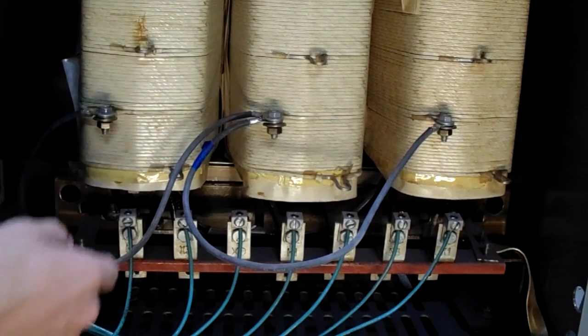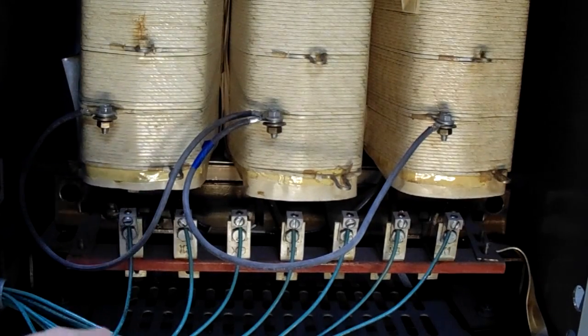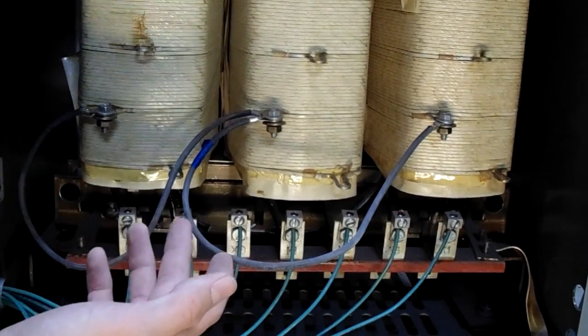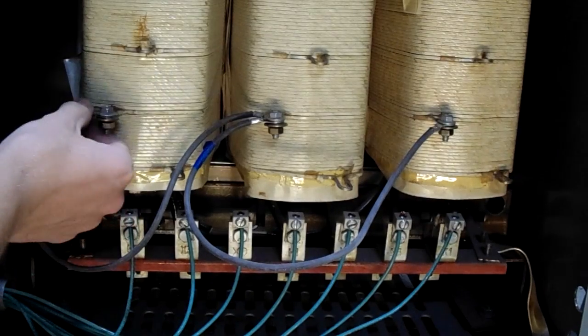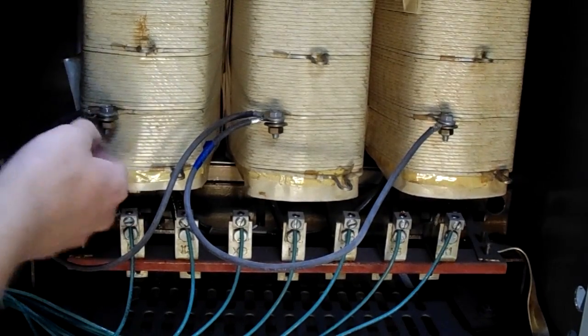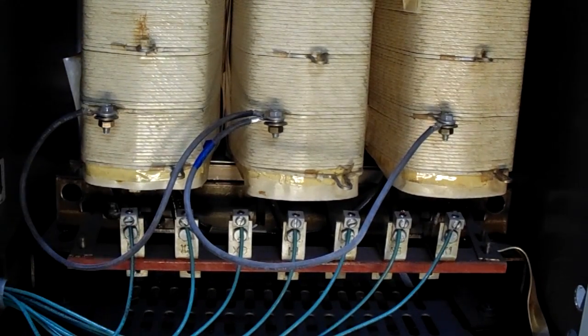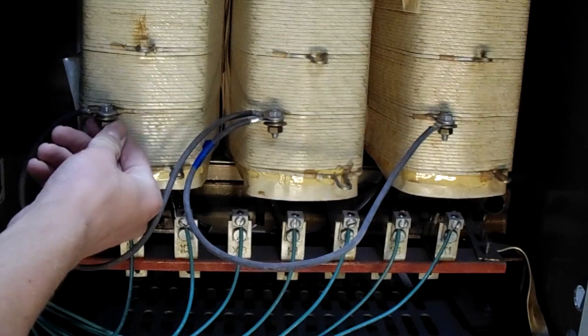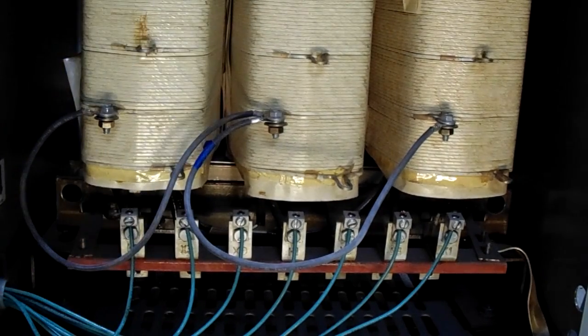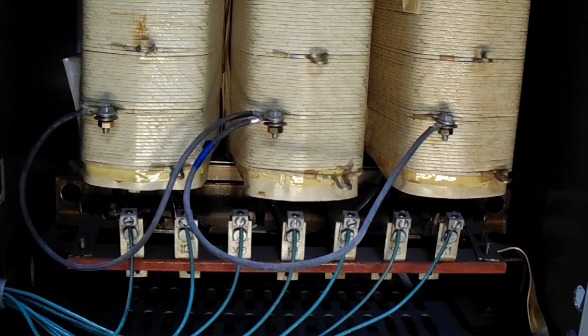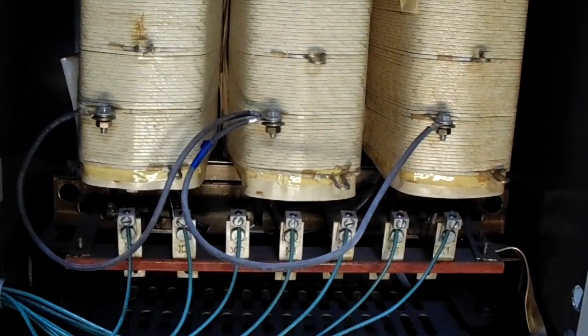I don't have another wire connected right now, but when I want to, or if I want to, I can add a crimp-on lug to a piece of 12 or 10 gauge stranded, and have a neutral in this high side star configuration. But anyways, if that's how you're planning to leave it, then you're done, and this is now a star-star transformer.